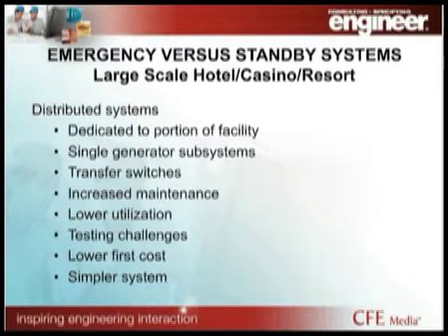Testing challenges are the other issue. Again, multiple locations that you've got to go test, multiple portions of the facility that you have to disrupt, unless you go with closed transition transfer switches, which we've seen both. There's certain large-scale properties whose approach is you go with code minimum. We don't care if our casino is down or if our hotel rooms are down or if we can't get to the central plant. If we have an outage, we're worried about first cost. And typically, a distributed system for a large-scale property will be driven by first cost. The other is, again, it's a simpler system. It's easier for a property operator to get their head around a generator with a series of transfer switches, and that occurs five times across the property, sometimes a little bit more, within their comfort zone.